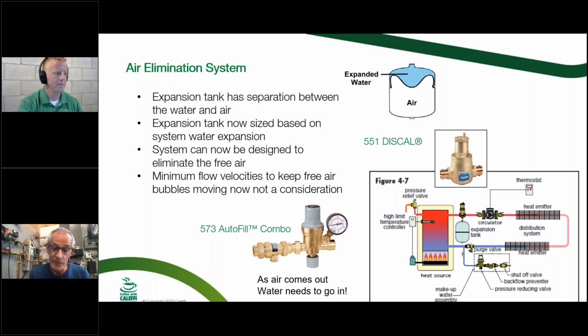We show a little fill valve there on the right, because as we're taking air out of the system for the first couple of days, perhaps we got to put water in behind it, or we're going to lose the pressure in our boiler and maybe go into a low water cutoff condition. So we want to fill water as we vent air out, and we want to get that air out at the hottest point in the system. In this picture here, you can see we've got it right at the top of the boiler there. That's where the air is going to come out of solution best.